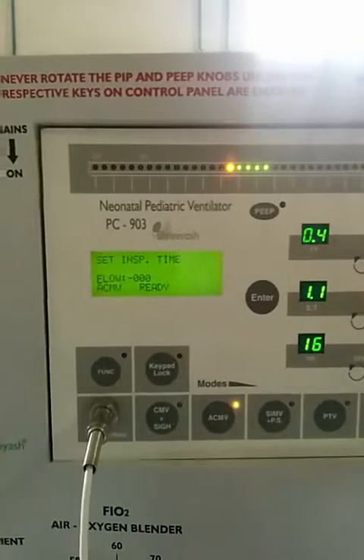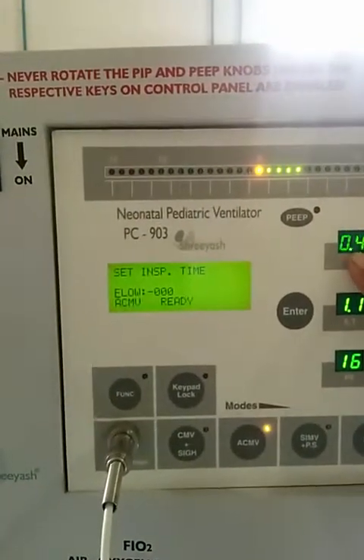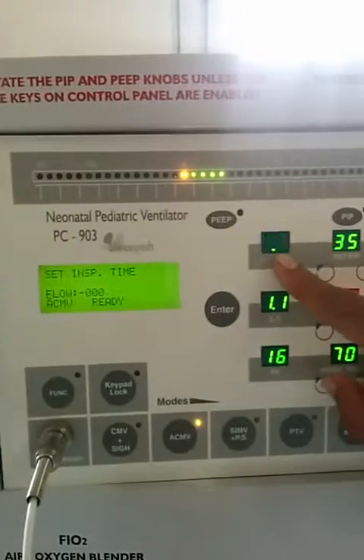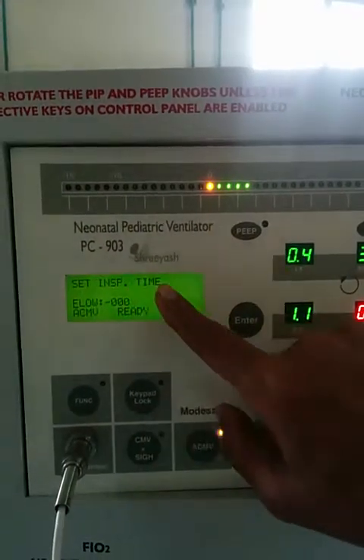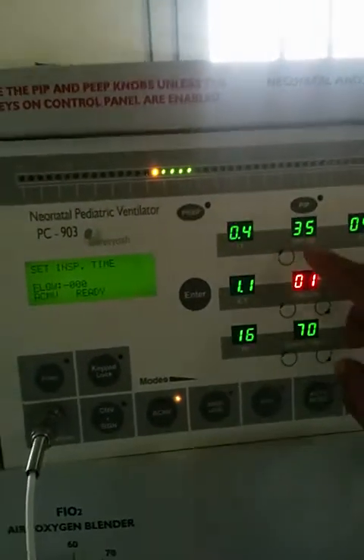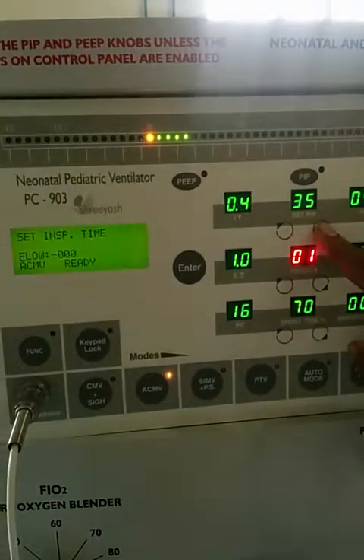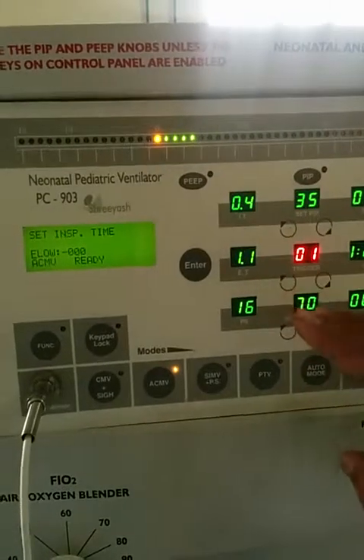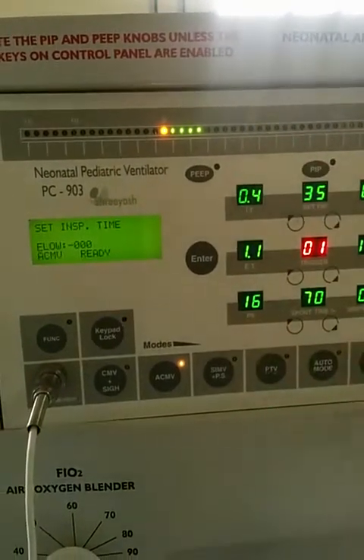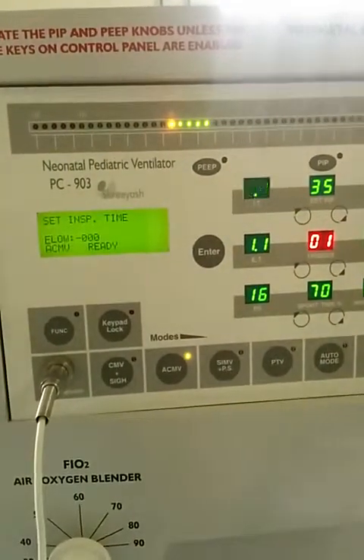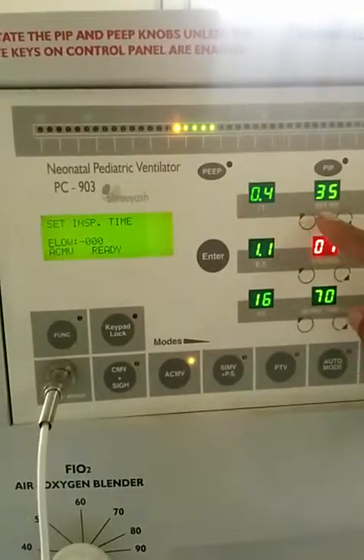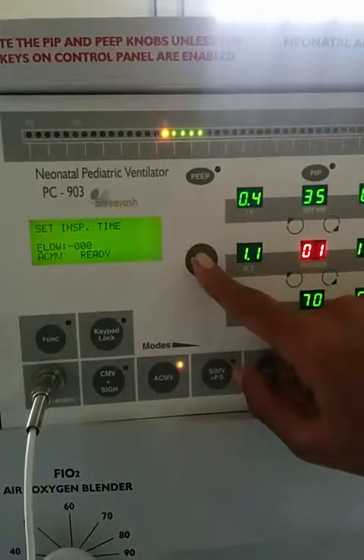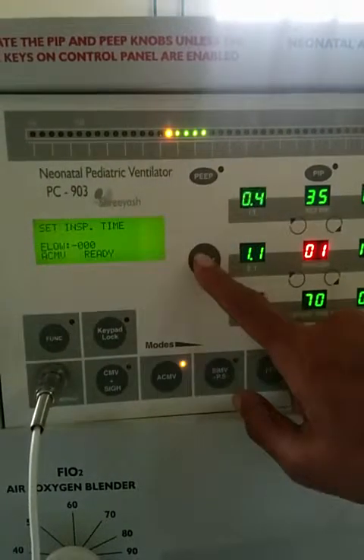Now you will notice that the display of inspiratory time is flashing. Simultaneously, the LED display indicates that you have to set the inspiration time. By using these up and down keys, you set the inspiration time. It can be set from 0.2 seconds to 3 seconds. So I set an inspiration time of 0.4 second, considering it's a neonatal case. Once I set this, I'll press the enter key to acknowledge the setting.